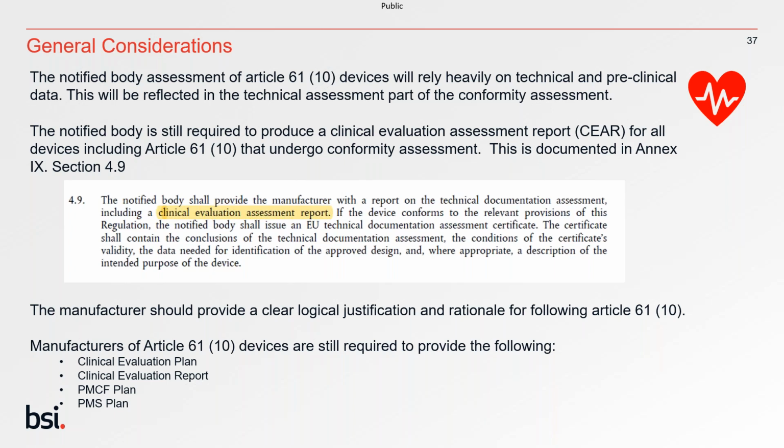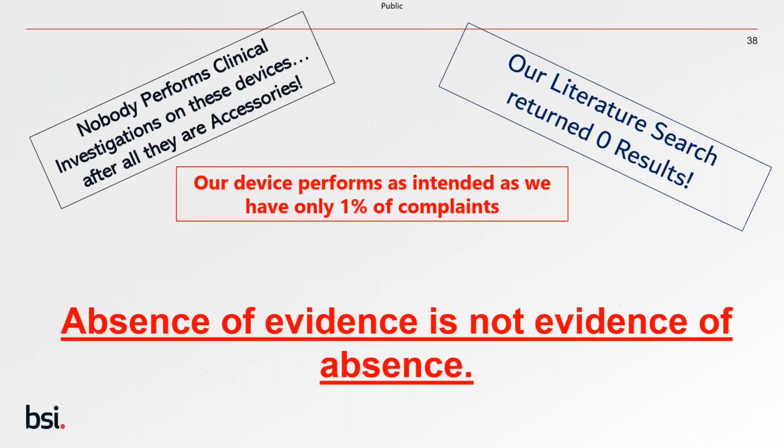It is worth saying, though, you still need to produce a clinical evaluation plan, because you need to define those GSPRs that could need clinical data, or justify why they don't need clinical data. We still expect a clinical evaluation report. We also expect a PMCF plan and a PMS plan.